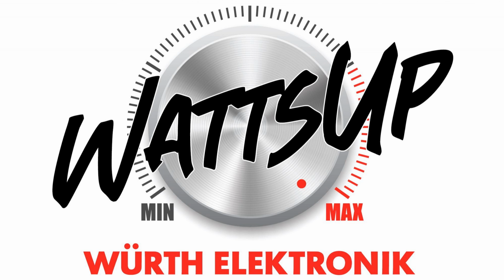So that's the noise that's injected into the mains lines. Then for the radiated emissions, it goes from 30 megahertz up to 1 gigahertz. Now, the FCC in the US actually only starts the conducted emissions testing at 450 kilohertz, which is a little bit higher.